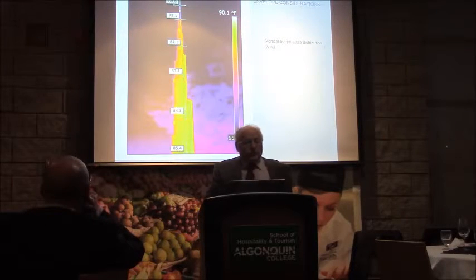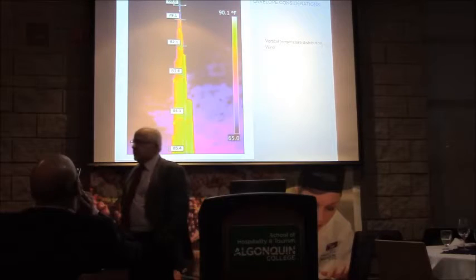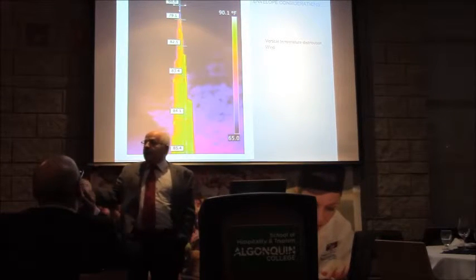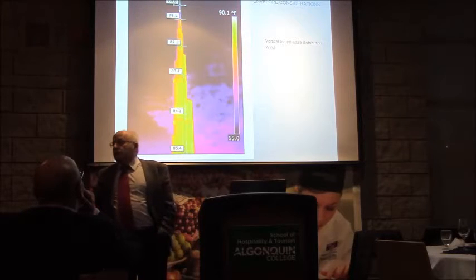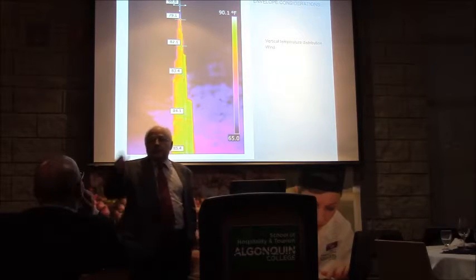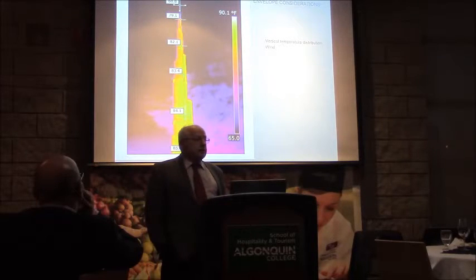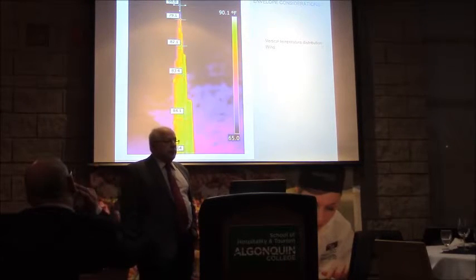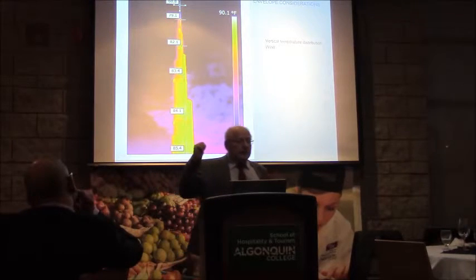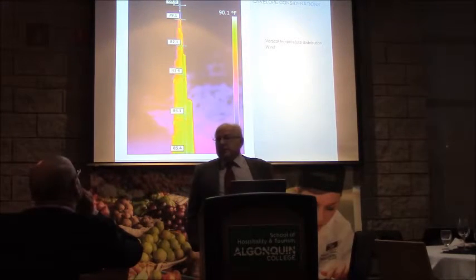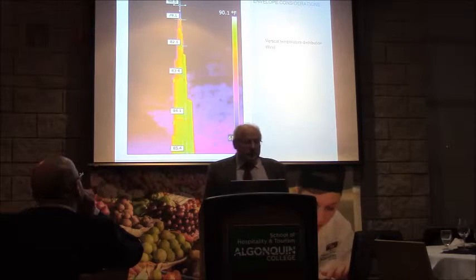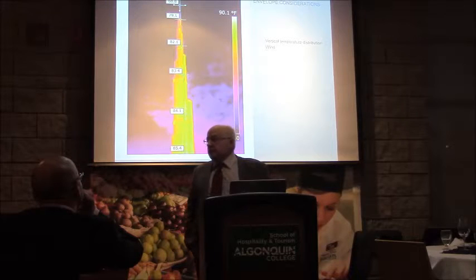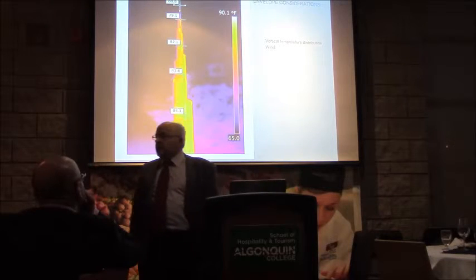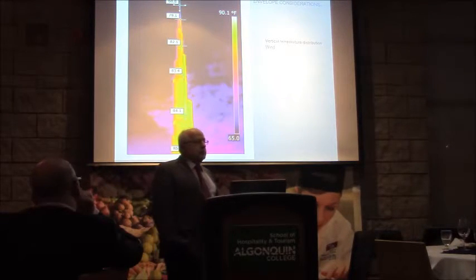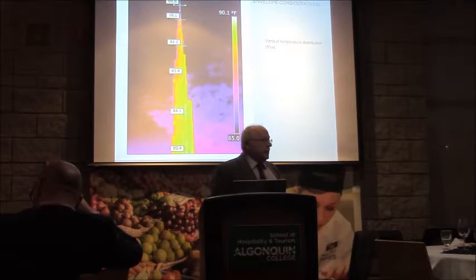One thing to be aware of, back to the Burj as an example, is that there's an adiabatic rate - as you go up from the ground, it gets colder. Anyone who's been in an airplane sees the screen say it's minus 50 or minus 60 outside - that's living proof of it. It occurs even at this scale. At the base of the Burj it was 85 degrees, at the top it was 68.8. So this has implications for our loads - there can be heat transfer between the lower and upper voids, with all kinds of opportunities and challenges.